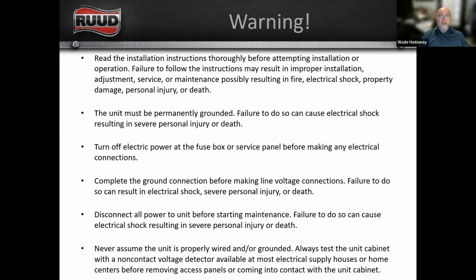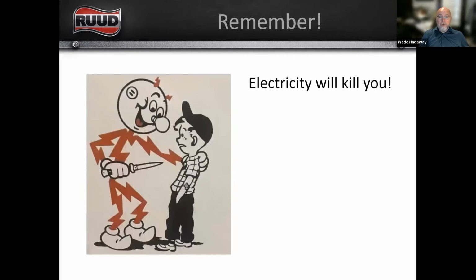Don't walk up to a condensing unit, and I'm terrible about doing this, and just put your hand or your arm on it and lean over it without making sure that it's grounded properly. It's very possible that if you have a short to ground or a dead short and there's not a good ground, that cabinet could be energized and you could get shocked or electrocuted. So we always want to be safe. Remember, electricity will kill you. Just don't be afraid of it. Just give it the respect that it deserves.